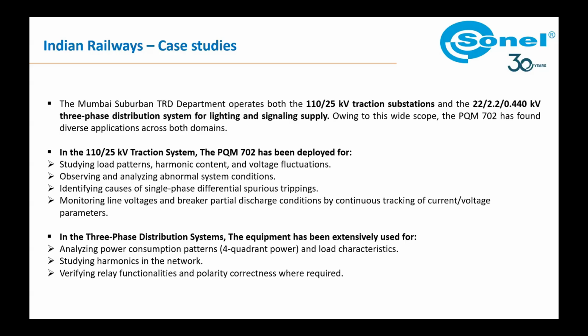Other than that, we have breakers. Over time, vacuum breakers can lose their vacuum and cause partial discharges in the VCBs. So we continuously monitor, in case there is a voltage issue in the line, even when the breaker is open, the PT voltage in seconds, milliseconds, or half cycles.